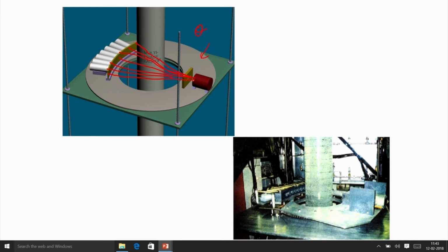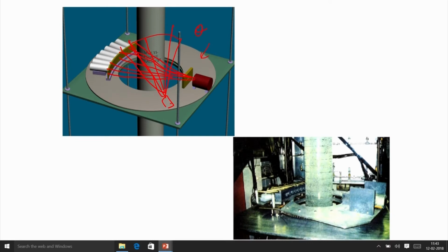So, for this theta suppose, you can move the source here and the detector somewhere will be aligned here, and again you will get this kind of scan. So, what you will do, you will scan with the theta, you will move this carriage in the theta direction. So, theta direction scanning is possible, r direction scanning is already done through the fan beam, theta direction scanning will be done. So, what you will get is a matrix.